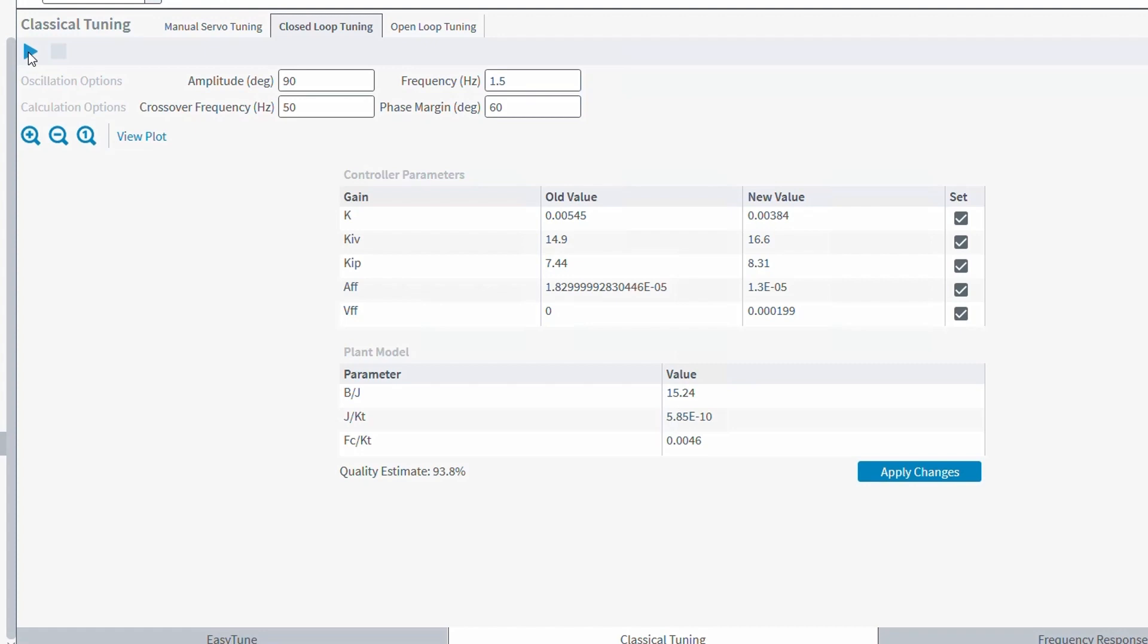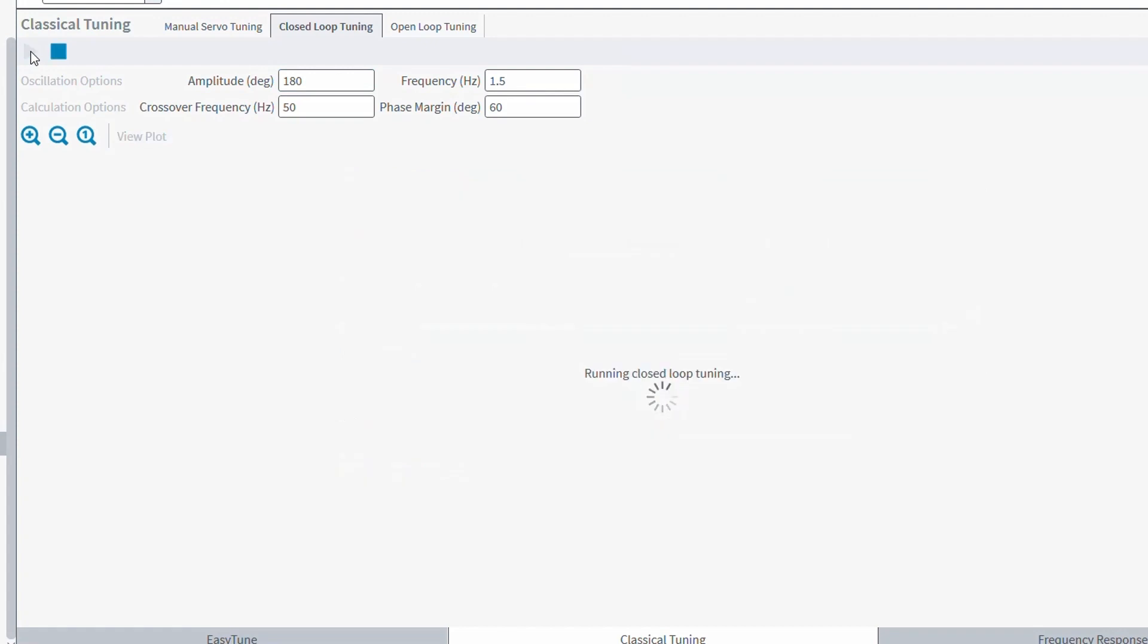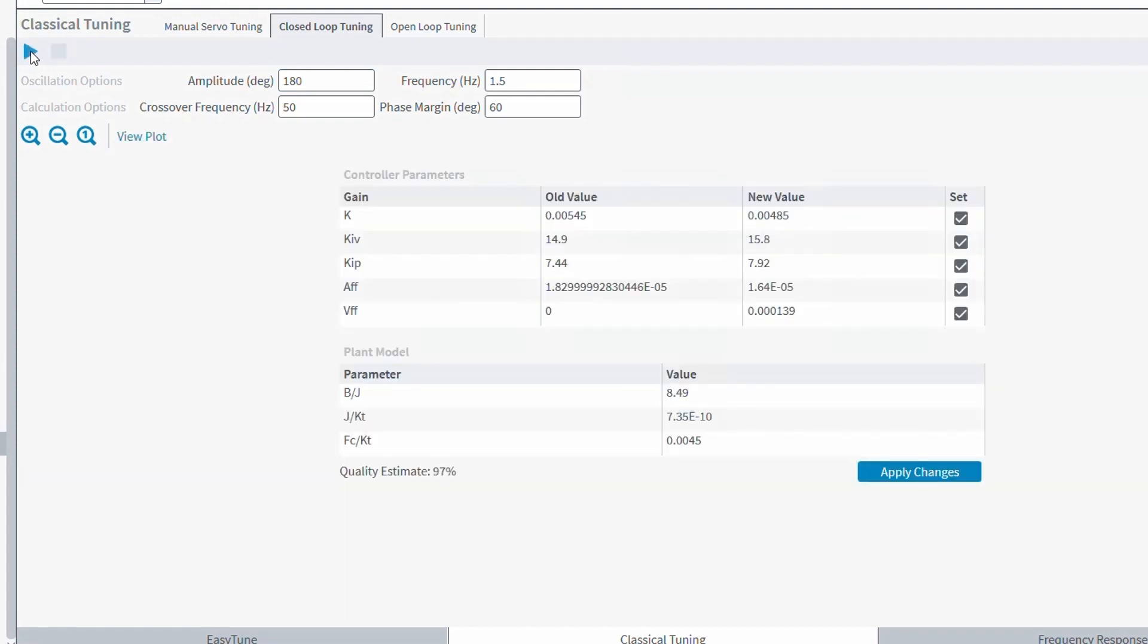Now, a quality estimate of 93% isn't bad, but let's see if I can get that better. To do that, I'm going to increase the amplitude to give my axis more travel so that it more accurately reflects the inertias in the system. I think a 97% quality estimate is pretty respectable, so I'll go ahead and apply those changes.